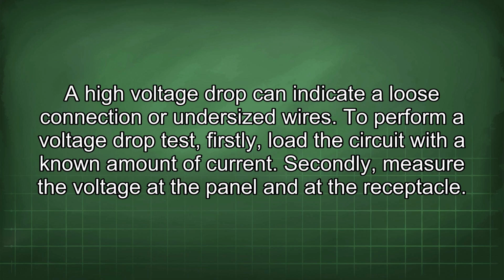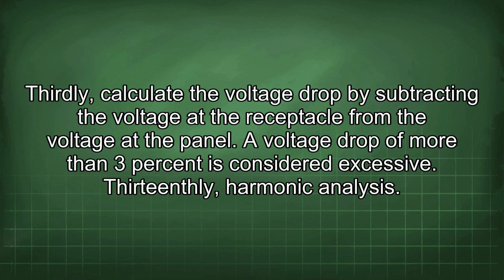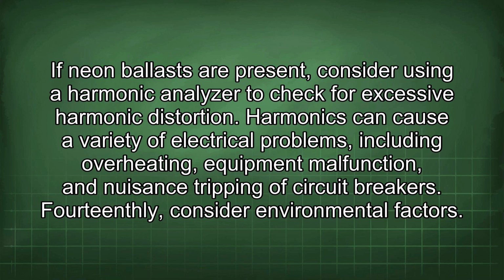To perform a voltage drop test, firstly load the circuit with a known amount of current. Secondly, measure the voltage at the panel and at the receptacle. Thirdly, calculate the voltage drop by subtracting the voltage at the receptacle from the voltage at the panel. A voltage drop of more than 3% is considered excessive. 13th, harmonic analysis. If neon ballasts are present, consider using a harmonic analyzer to check for excessive harmonic distortion. Harmonics can cause a variety of electrical problems, including overheating, equipment malfunction, and nuisance tripping of circuit breakers.